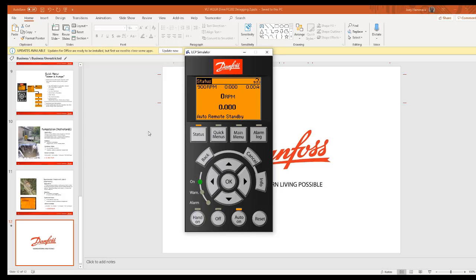But as far as which is better, I think power is used because we're using the motor as a sensor in this case, and it's one of the things the drive is monitoring all the time, and it's more real to what the motor is using, because we're doing it not necessarily at current all by itself, it's current at a speed, so it's doing it at a power level. Could we have done it with amps? Yeah, or torque, but I think in the water application, we don't always focus on torque per se as it would be in an industrial side of things. So I think it was probably just a choice that power is a function of current and torque, and so power was selected. Okay, great. Thanks.